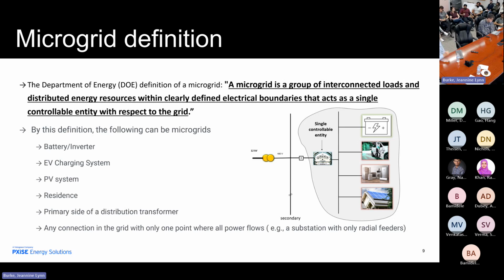Now, this is how we see the microgrids being operated. You have a 480 volt connection to a meter. That's the single controllable entity. You have uncontrollable loads behind this device. And our goal is to control the flow at that point of interconnection.